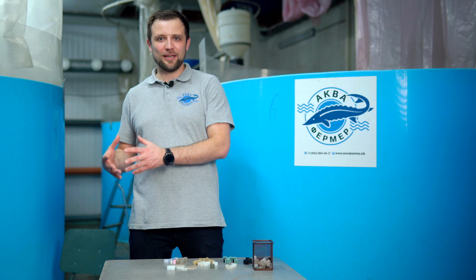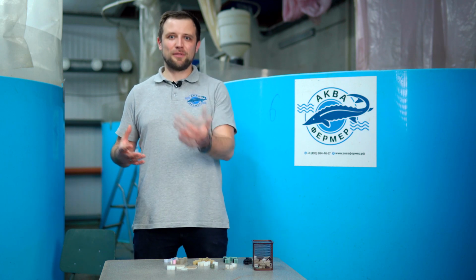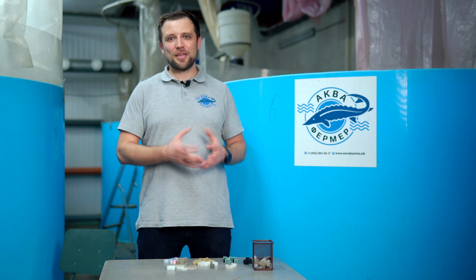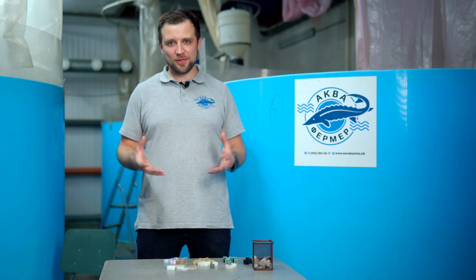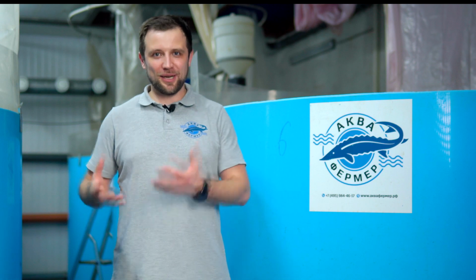So, what is water biological treatment and what is its function? It converts ammonia first to nitrite NO2 and then to nitrate NO3. Nitrates are considered to be a relatively harmless form of nitrogen and are safely flushed out with the makeup water. So, to make this biological treatment work, we need bacteria in RAS. And that's why this type of water treatment is called biological, because it's carried out by living microorganisms. The bacteria have to be constantly in RAS.